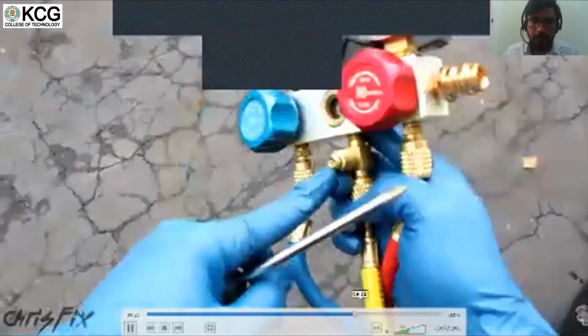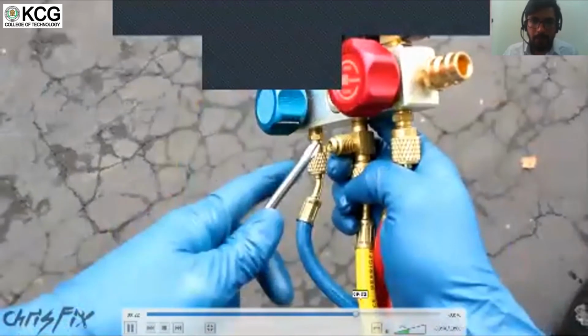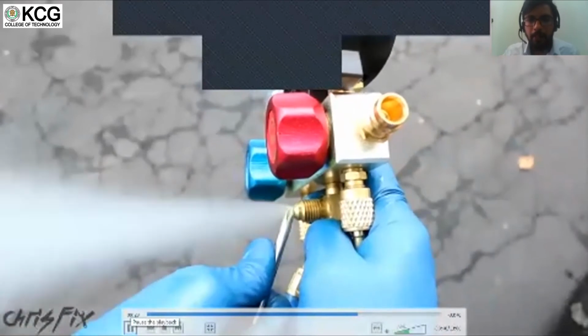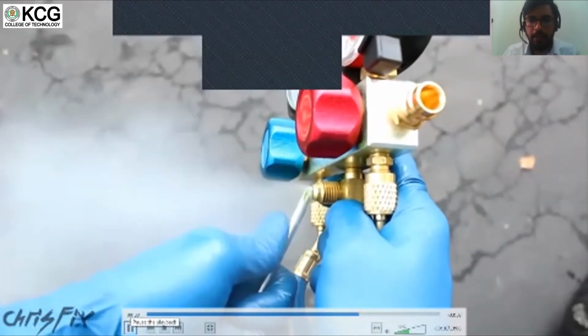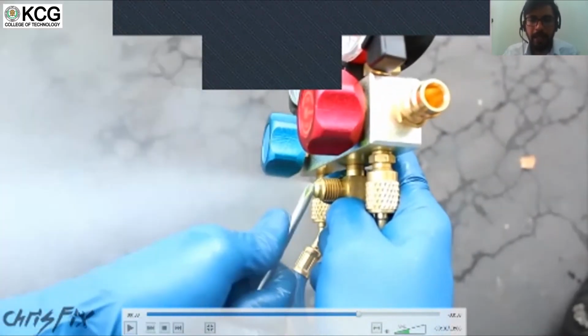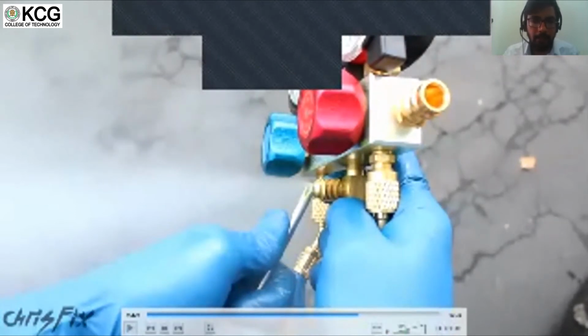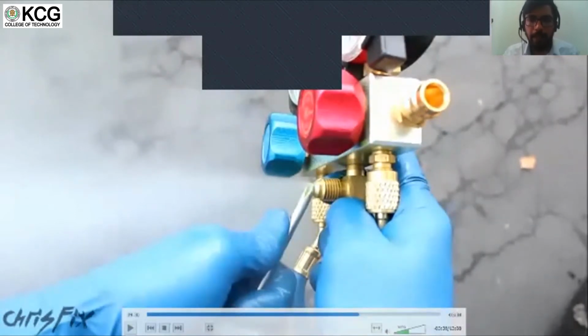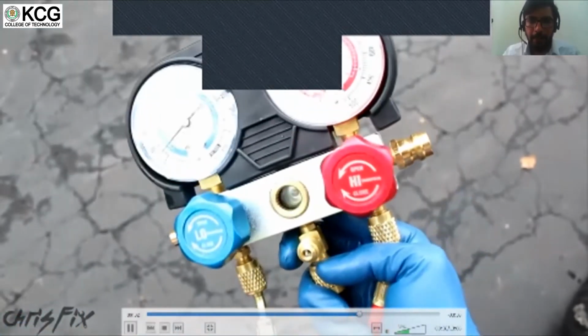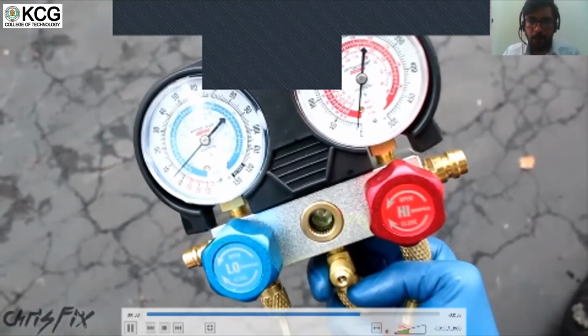What you do to purge the line of air is you get a screwdriver, you go to this purge tip right here. This is a very important step, that it removes the air, whatever residual air was inside the line. As this purging will remove the complete air. So now you have complete refrigerant, until the refrigerant comes out, and now we have purged the system of any air.